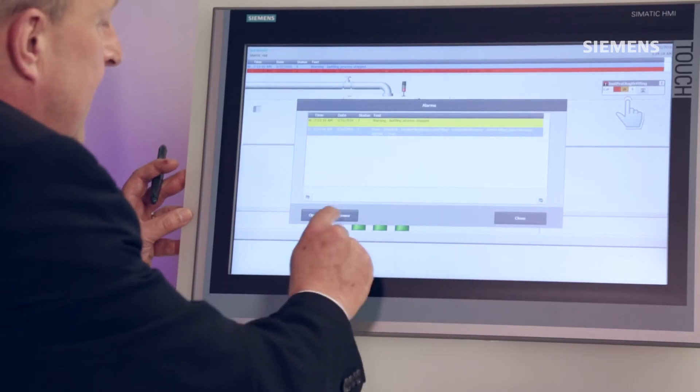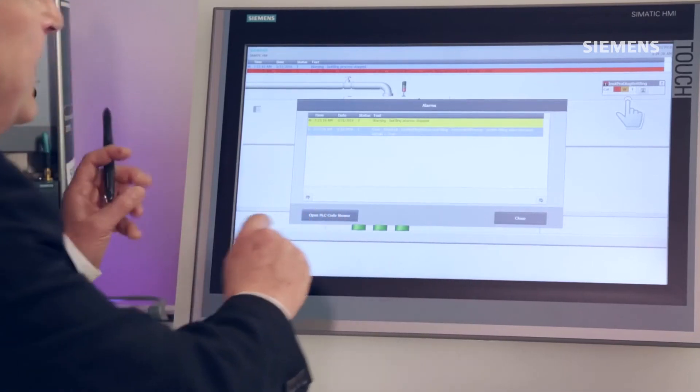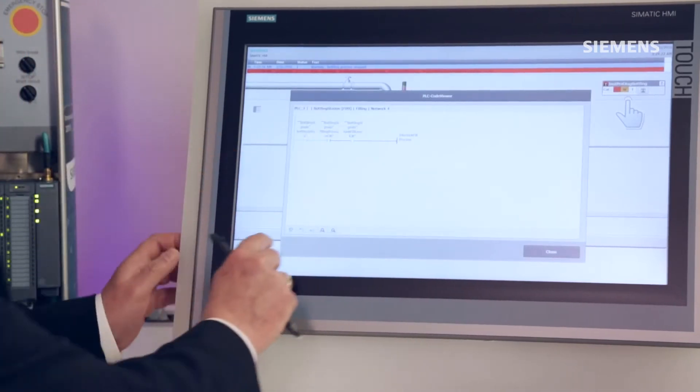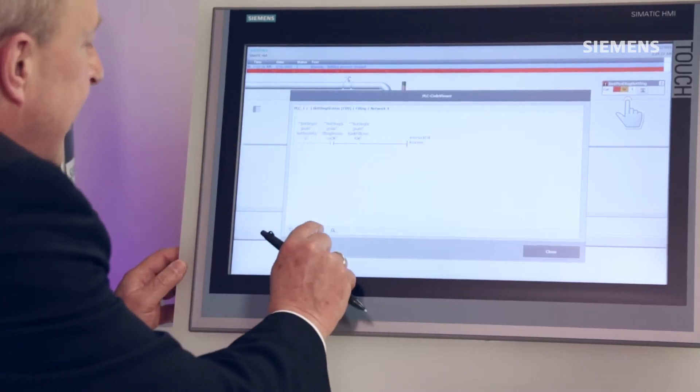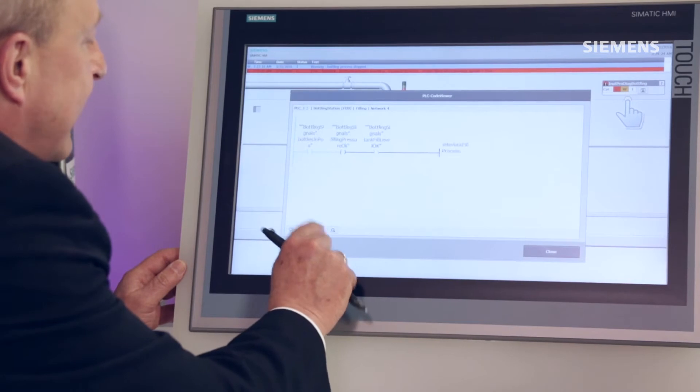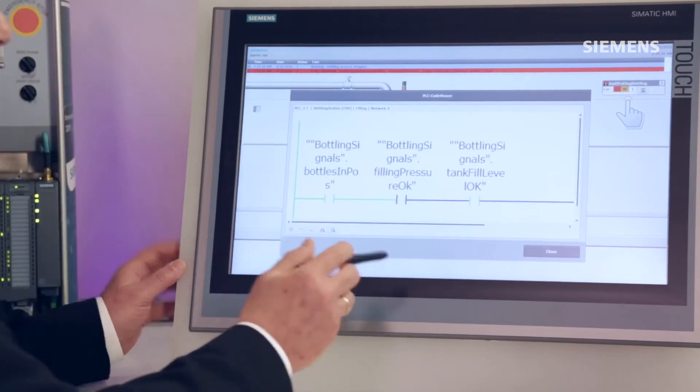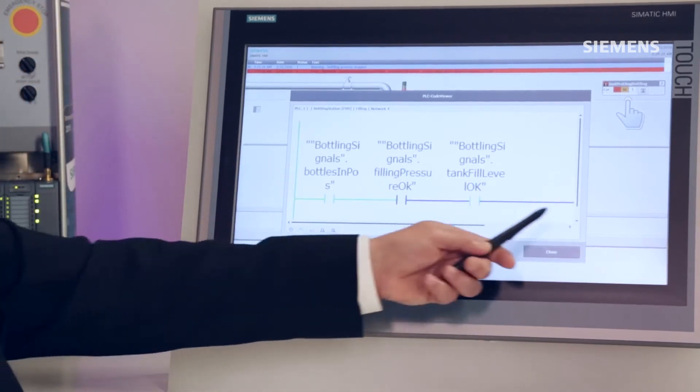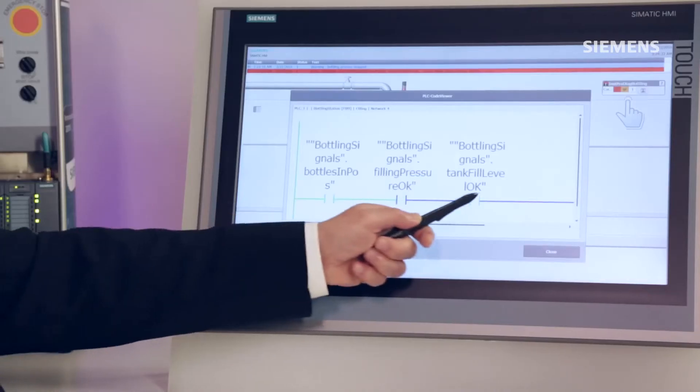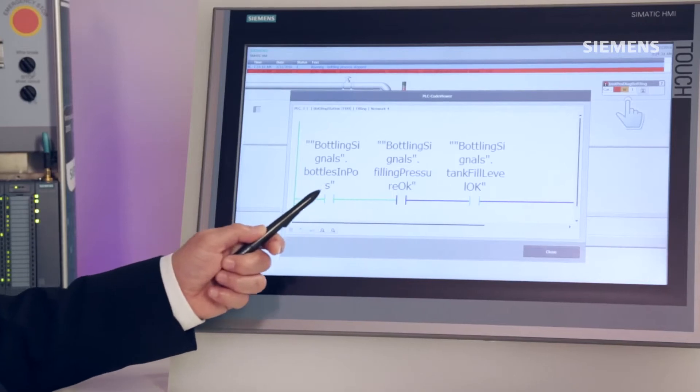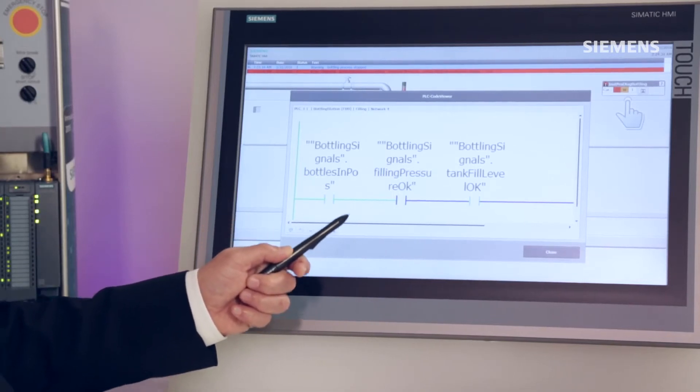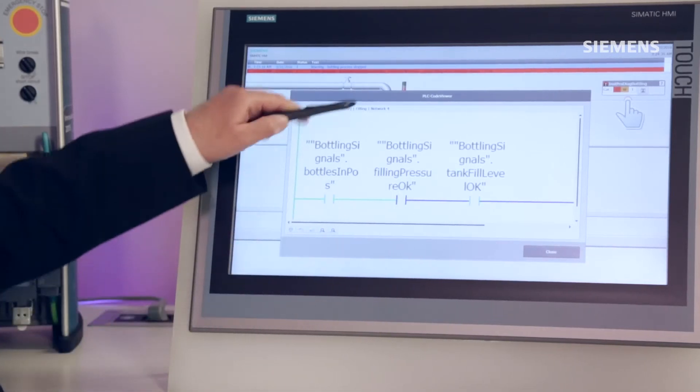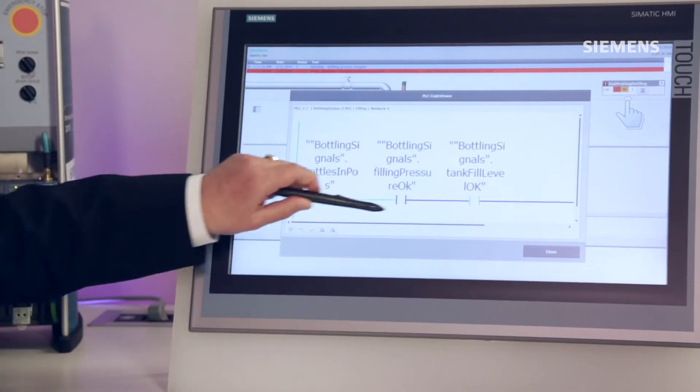So I open my PLC code viewer to learn more. Here, I get a clear display showing precisely why the release for onward bottling has not been given. Namely, because an upstream interlock condition has not been met. In this case, the release has simply not been given or the alarm report has been received that inadequate pressure for filling operations is available.